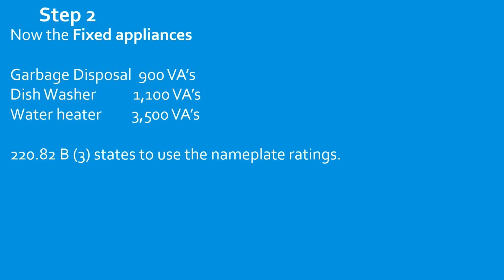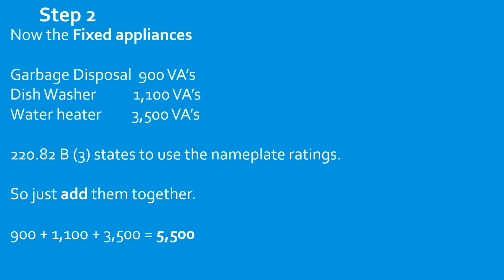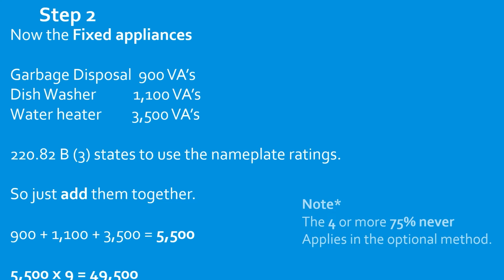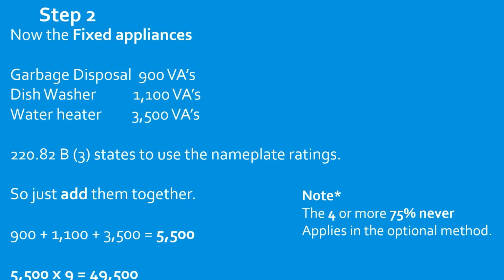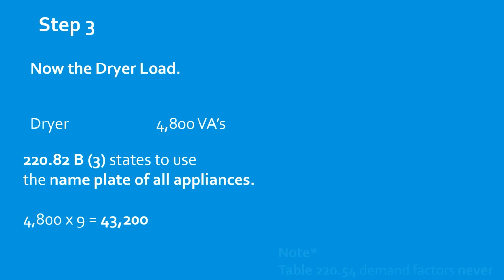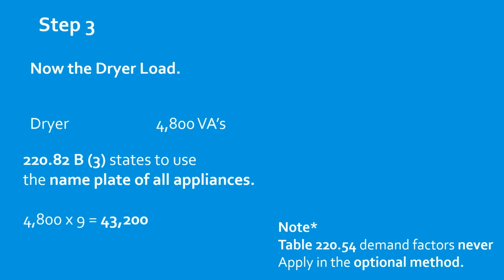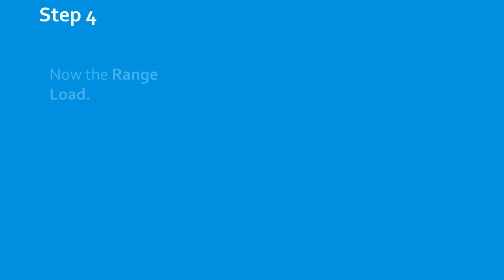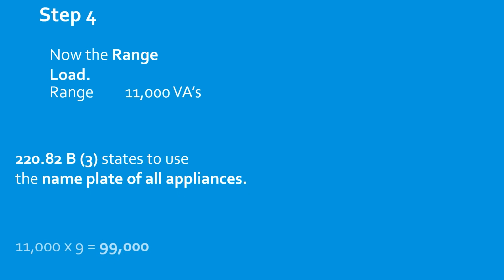Fixed appliance. Step 2. Now let's do the fixed appliances. The optional method's easy. We're just going to use the nameplate ratings. We add them all together, and then we multiply it by however many units we're doing. So it's 49,500 VAs. Note, the 4 or more 75% rule never applies in the optional method. Same thing with the dryer and nameplate. Boom. And you're never going to use the dryer tables when using the optional method. Same thing with the ranges. Boom. Multiply it by the amount of units, 99,000.